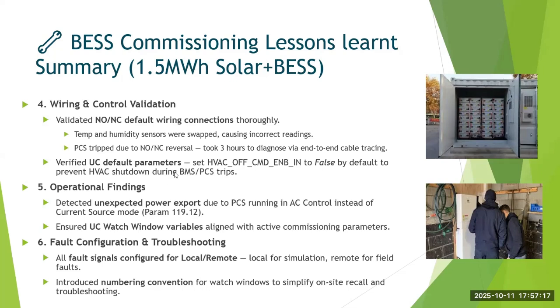Then the software side, we need to have the proper variables defined with default values, which ensure that the BMS, because we have a battery management system, PCS, HVAC, and the fire system, all have their initial conditions and variables in the software logic properly defined. What happened in our logic on the base BMS PCS was that the HVAC remote enable should ideally be on, which means I can switch HVAC on and off and it should be able to operate remotely. If that parameter was set wrong, I can't operate HVAC remotely.